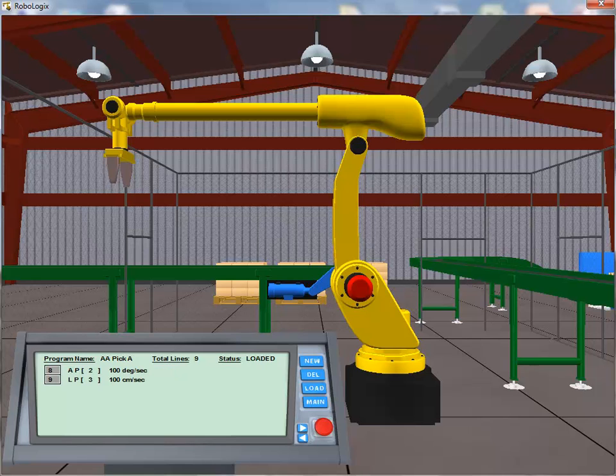With the robot arm now positioned directly over Conveyor 2, we use a Linear Motion instruction to bring the arm down to a position from which we can drop the box onto the conveyor. Once again, we have a new unique position that requires a separate and individual position register index number. With the TCP now located just inches over the second conveyor, it's time to open the gripper and drop the box onto Conveyor 2.